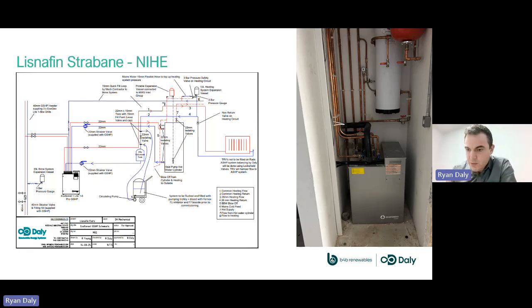And then the picture on the right shows the mini heat pump, the EcoForest EcoGeo Lite 1 to 6 kilowatt ground source heat pump. That's a small inline buffer tank just to increase the volume of the system a wee bit as well, which is probably more a thing for the air source heat pumps when you're required to do a defrost, but we put them in for the ground source as well.